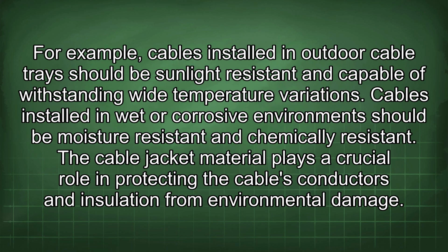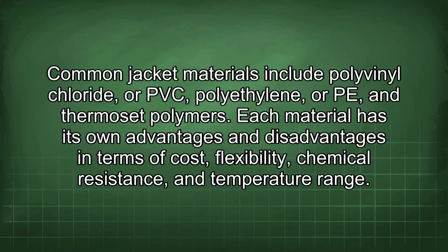For example, cables installed in outdoor cable trays should be sunlight resistant and capable of withstanding wide temperature variations. Cables installed in wet or corrosive environments should be moisture resistant and chemically resistant. The cable jacket material plays a crucial role in protecting the cable's conductors and insulation from environmental damage. Common jacket materials include polyvinyl chloride, or PVC, polyethylene, or PE, and thermoset polymers. Each material has its own advantages and disadvantages in terms of cost, flexibility, chemical resistance, and temperature range.